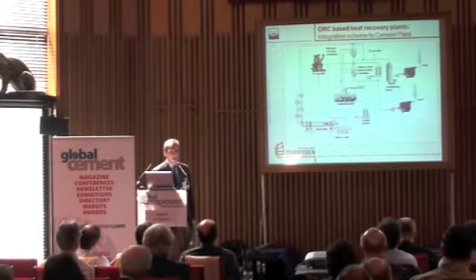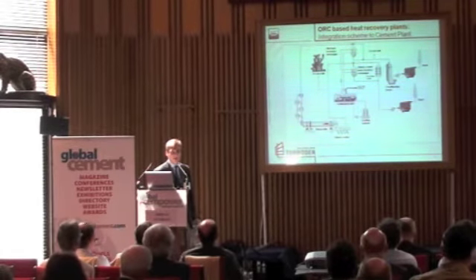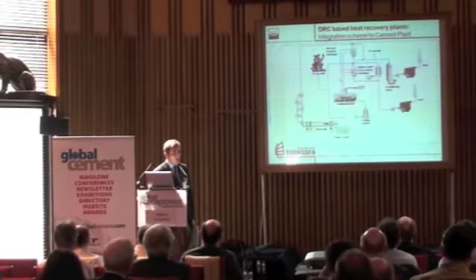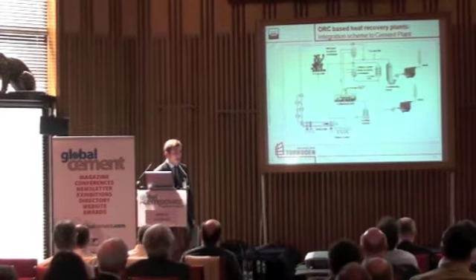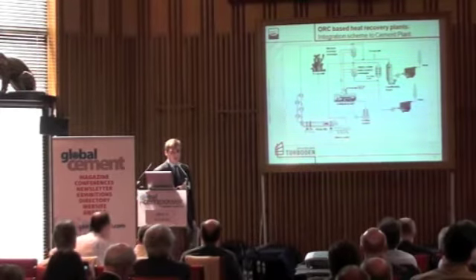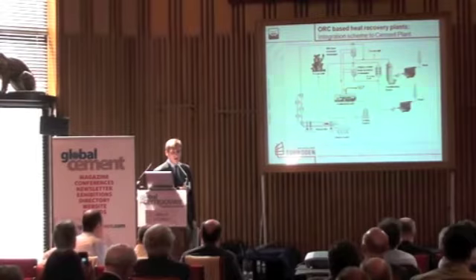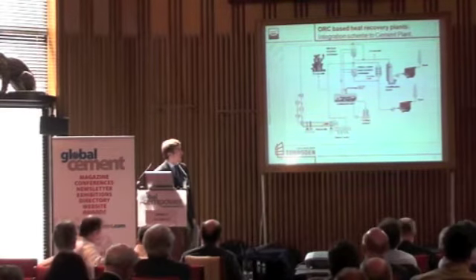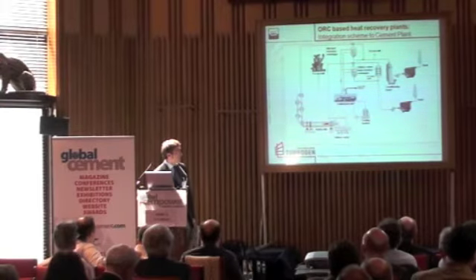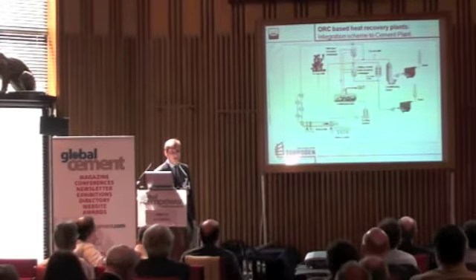So, as all of you know, there are two main heat sources: the preheater hot gases, and the kiln clinker cooler gases. We couple with these heat sources installing either a thermal oil heat recovery exchanger or a pressurized water exchanger, or in certain cases we could also employ a saturated steam heat recovery exchanger, where we collect the heat present in the exhaust gas to deliver it to the ORC power block, which is where we really take this heat and convert it to electrical power.